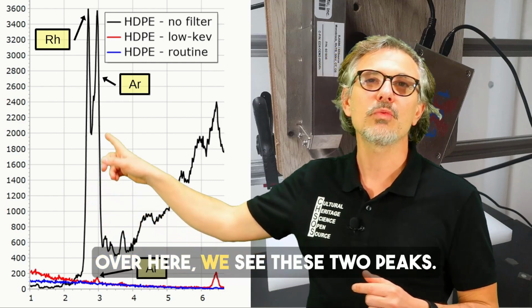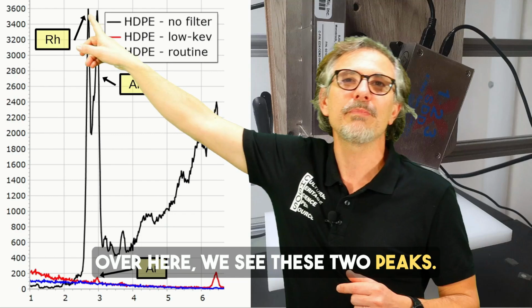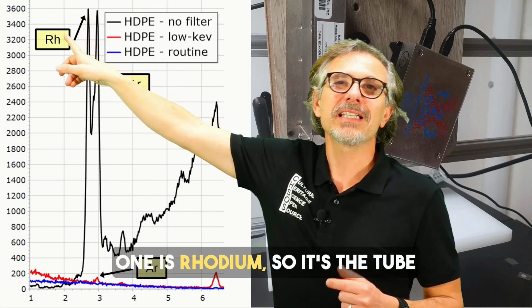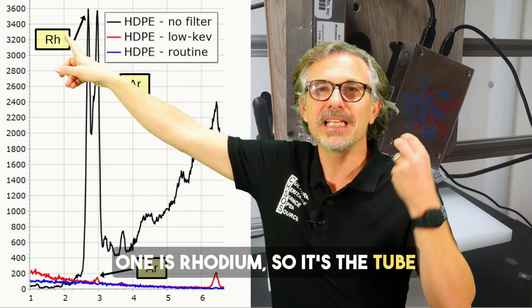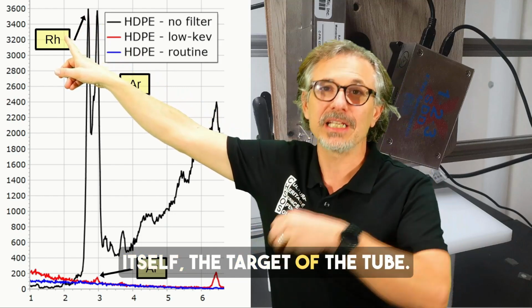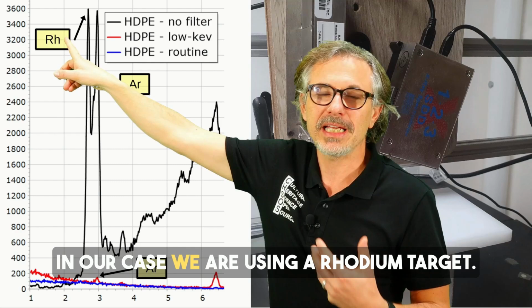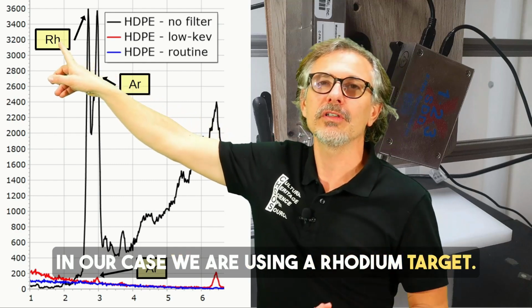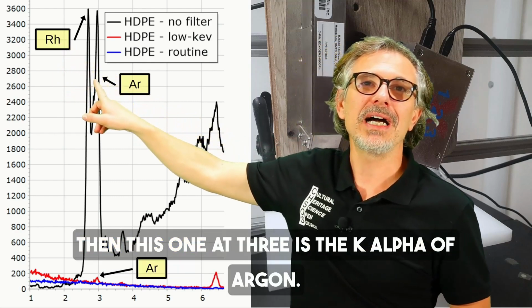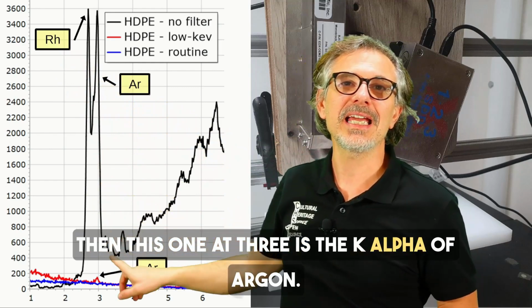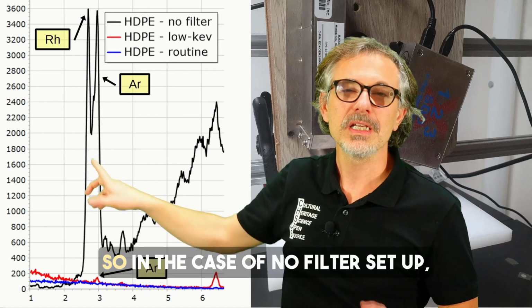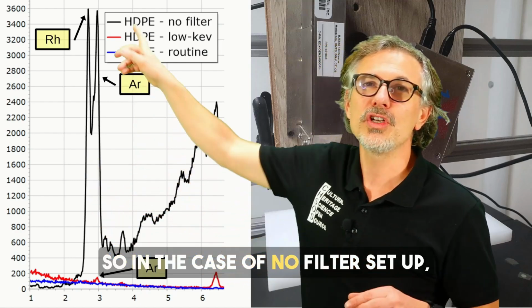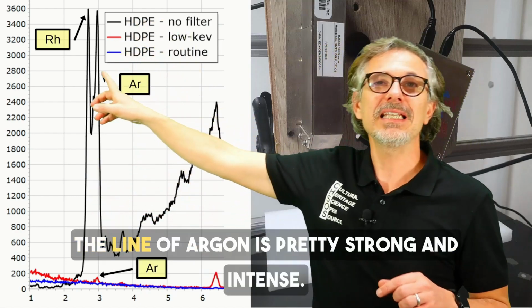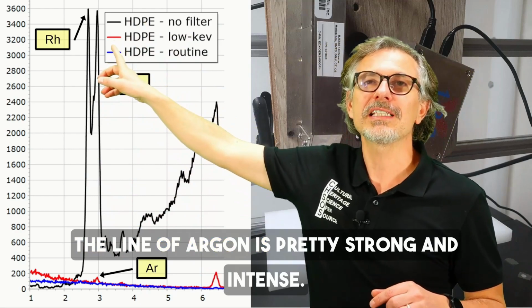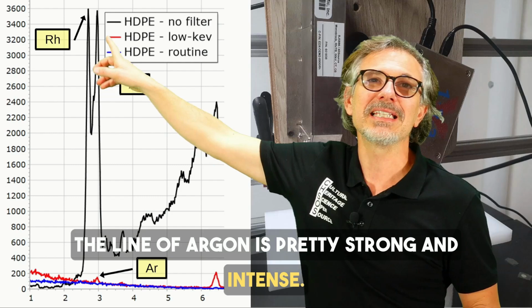Over here we see these 2 peaks. One is rhodium, so it's the tube itself, the target of the tube. In our case we are using a rhodium target. Then this one at 3 keV is the K-alpha of argon.